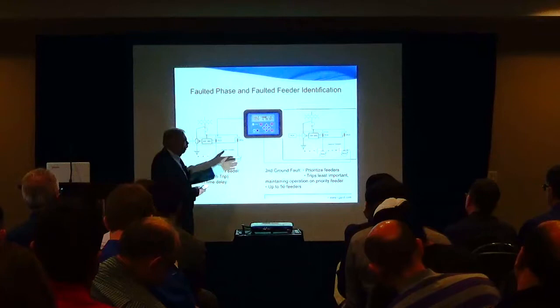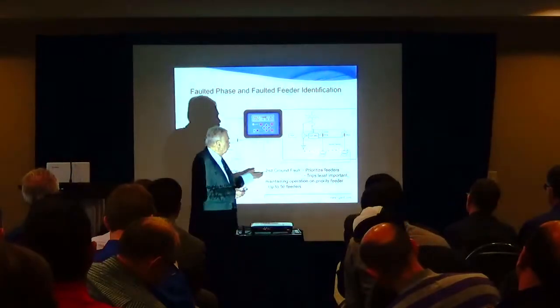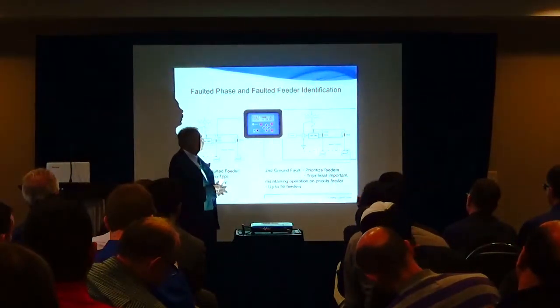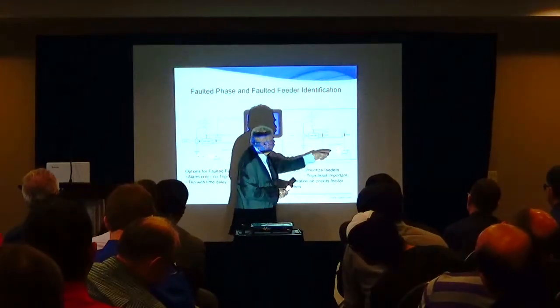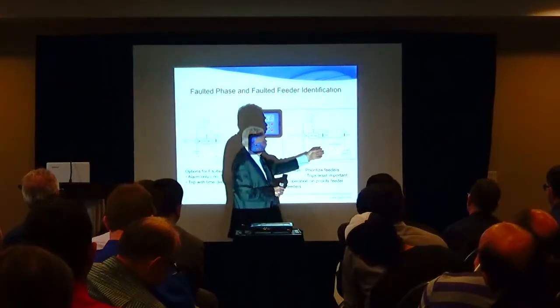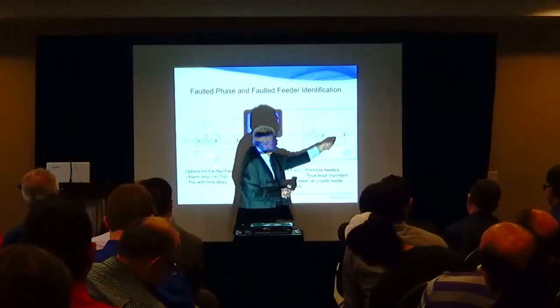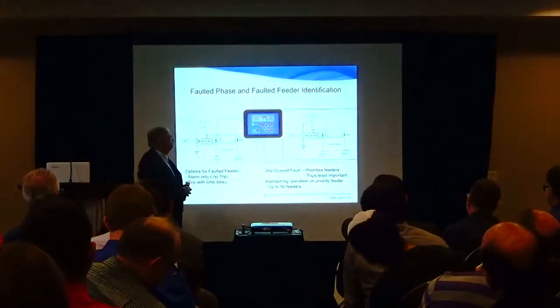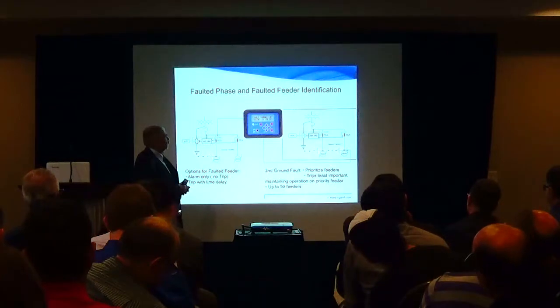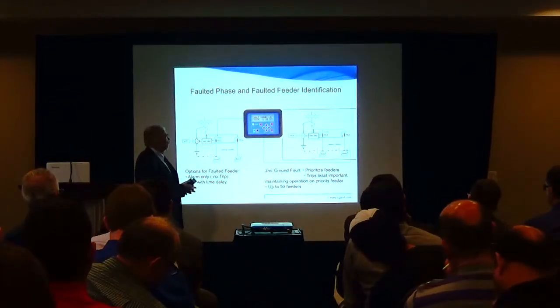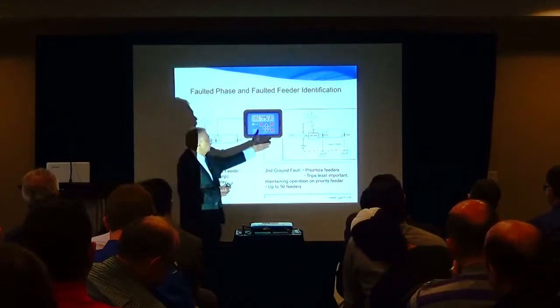Then he would have the option of putting a second ground fault setting, so that if you get a second ground fault here, then you have a phase-to-phase situation through the bonding conductor. A serious fault current will flow, so these two sensors will see it, and you only need to trip one of them, you don't need to trip both. One would isolate that line-to-line condition, and then you go back to a single fault, which you can have with 5 amperes controlled by the resistor.